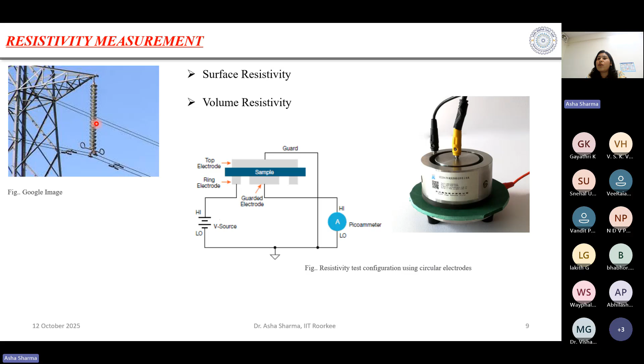If I represent this insulator string equivalently in terms of R and C, I don't know whether these R and C are connected in series or in parallel. So our main concern is not to measure the C here, our main concern is to measure the dielectric loss R. This dielectric loss measurement is also called the loss tangent or dielectric loss angle, and it is represented as tan delta.